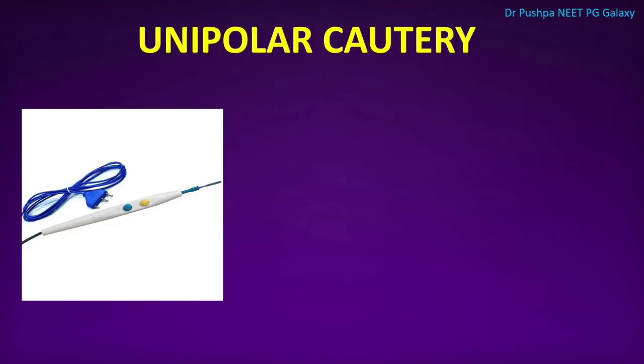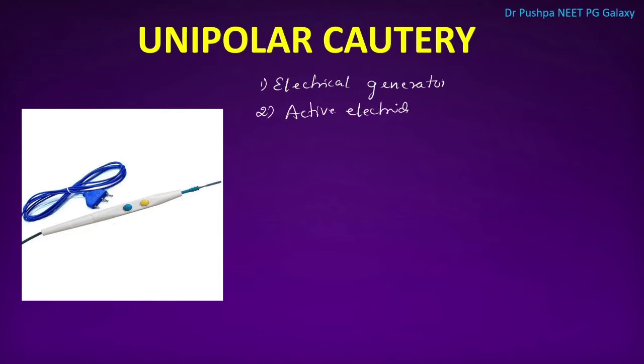In monopolar or unipolar cautery, the electrosurgical unit consists of an electrical generator, an active electrode where current enters the patient, and a return electrode where current exits. The handle tip is the active electrode, whereas the grounding pad is the return electrode.